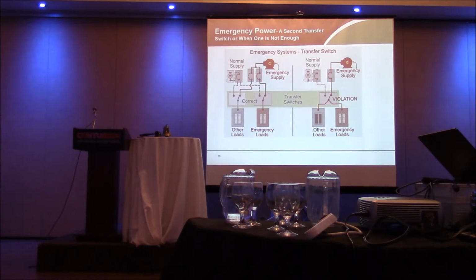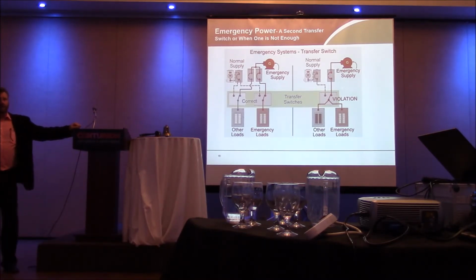So if you're called in to do a project inside of the building, and you know, the nice folks at the condo say to you, well, we want to put our domestic water booster pump on emergency power, then your answer should be, sure, you got a second transfer switch. You got the second. Like literally, I did an evaluation in the building 2 years ago, and they couldn't figure out why their generator kept stalling. Every time we had one of those massive deluge rainstorms, went in and found out that all of the sump pumps in the building and the parking garage were hooked to the emergency generator. And when all those sump pumps ran at the same time, it overloaded the generator and the generator stalled.